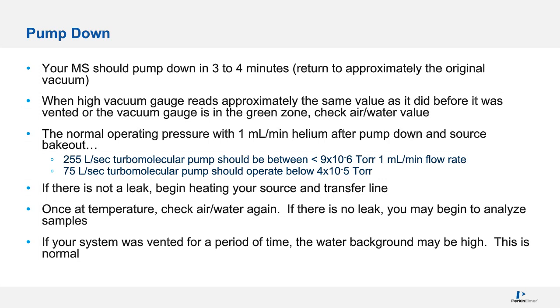The normal pressure for a 1 mL per minute flow rate is less than 9 times 10 to the negative 6 torr. On a 2 mL per minute flow rate, it's usually 1 times 10 to the minus 5, which is fine. That's on a 255 liter per second big turbo. If there's not a leak, pump down takes around 3 to 4 minutes.